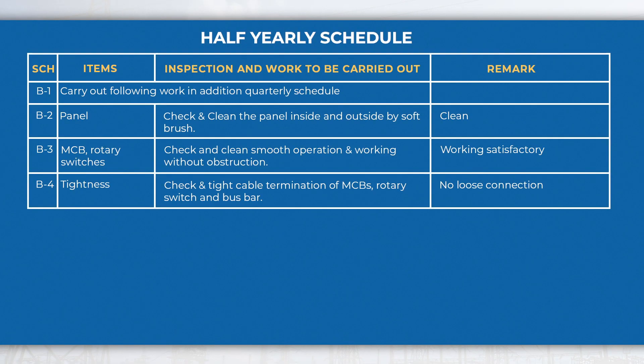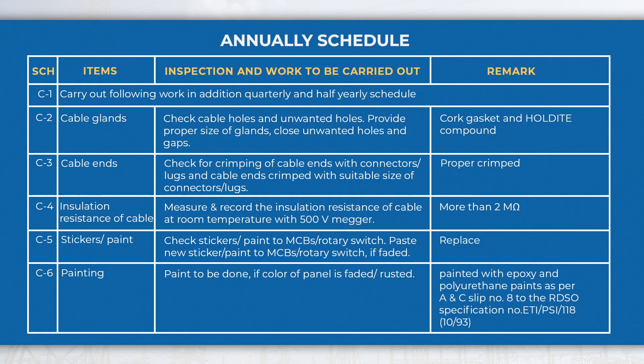In the half-yearly schedule, perform activities like checking and tightening all cable terminations, etc., in addition to quarterly schedule activities. In the annually schedule, perform activities like measuring the insulation resistance value of cable and checking of cable, etc., in addition to half-yearly and quarterly schedule activities.